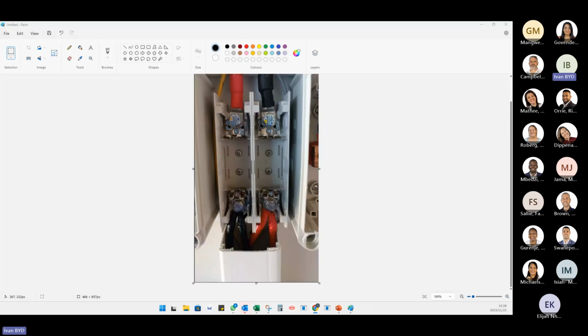So BYD batteries have a pre-charge resistor in them. What will happen is the brain of the battery will turn on. It'll go into a pre-charge mode and it'll test. It'll try with a resistor, so very little current can flow, and try to get the DC bus up to 48 volts. And if it detects a short circuit or an inverter connected incorrectly, it won't turn on fully, and it will give a short circuit error.